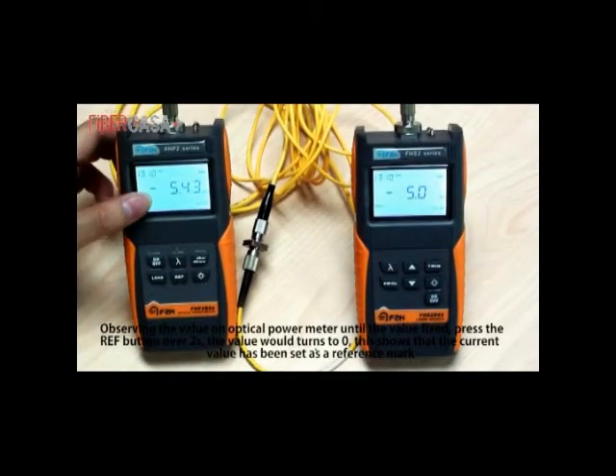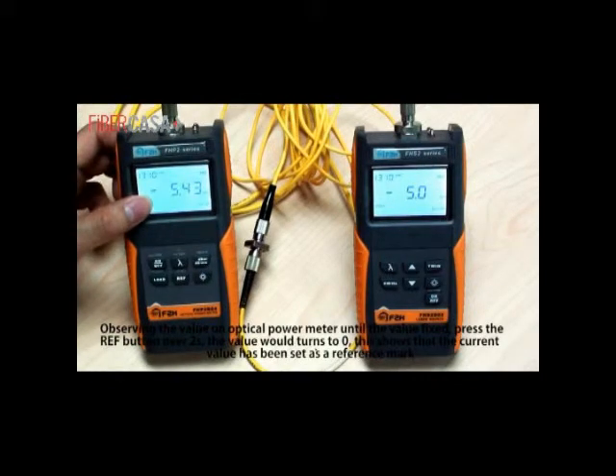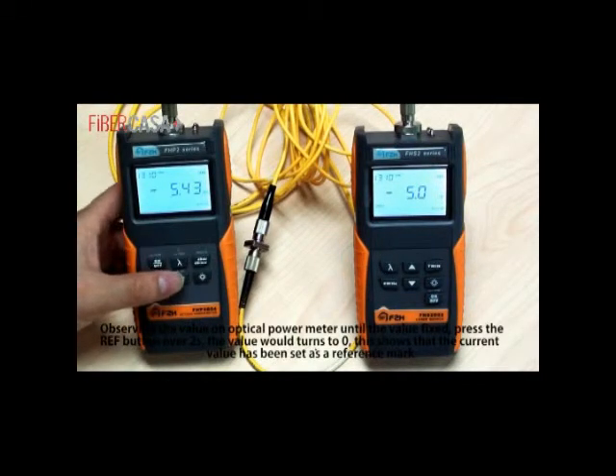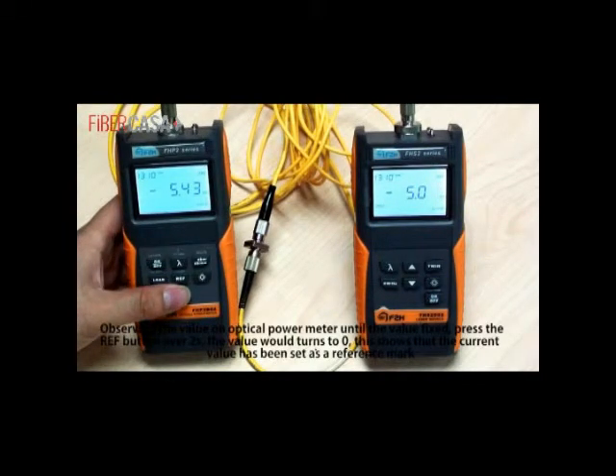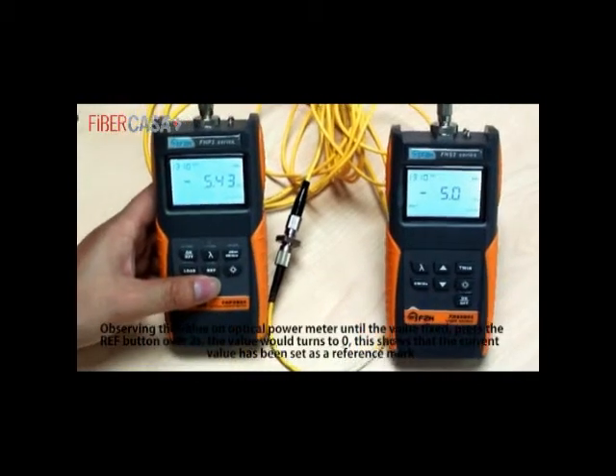Observing the value on optical power meter, until the value is fixed, press the REF button over 2 seconds. The value would turn to 0. This shows that the current value has been set as reference mark.